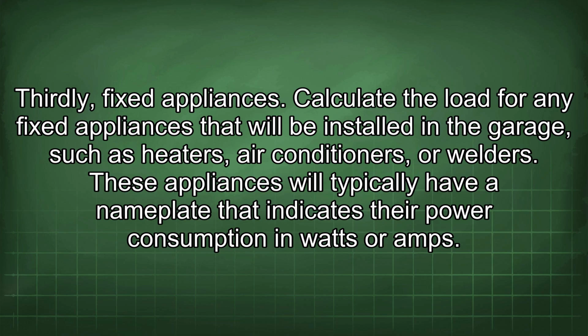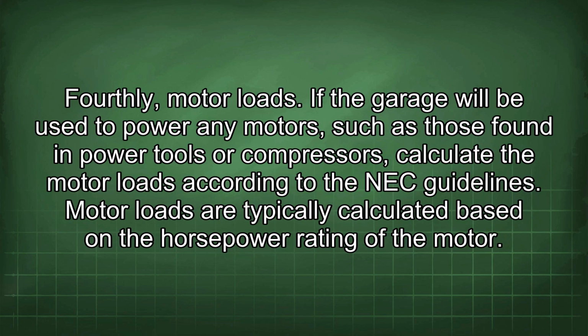Thirdly, fixed appliances. Calculate the load for any fixed appliances that will be installed in the garage, such as heaters, air conditioners, or welders. These appliances will typically have a nameplate that indicates their power consumption in watts or amps. Fourthly, motor loads. If the garage will be used to power any motors, such as those found in power tools or compressors, calculate the motor loads according to the NEC guidelines. Motor loads are typically calculated based on the horsepower rating of the motor.